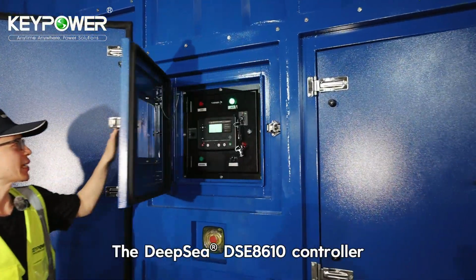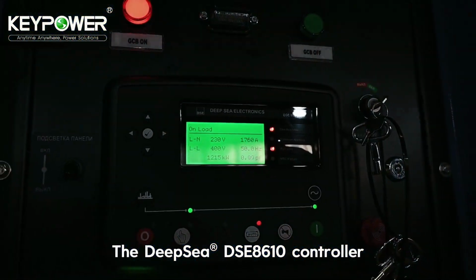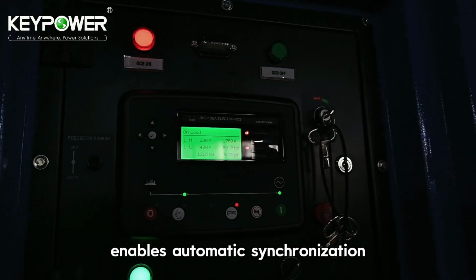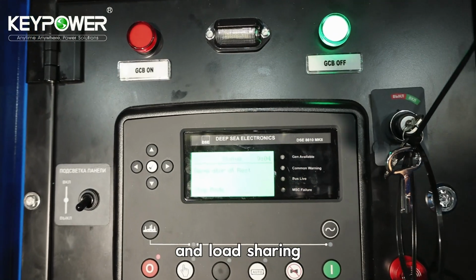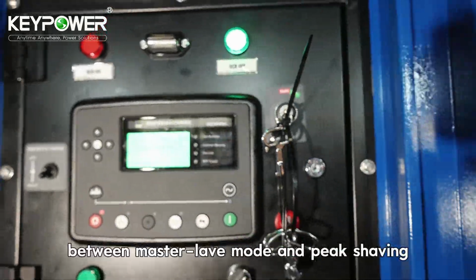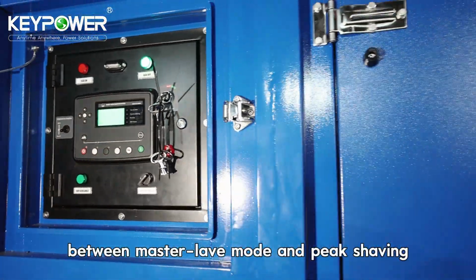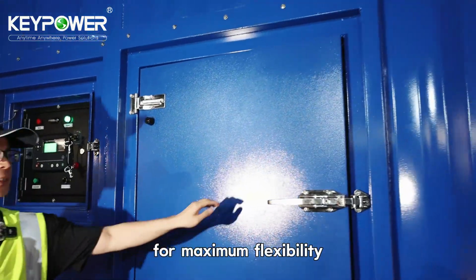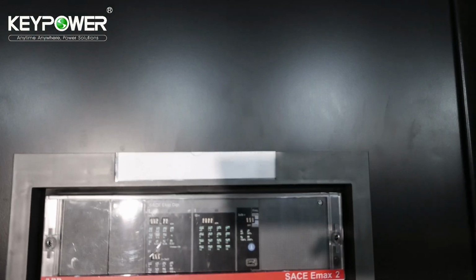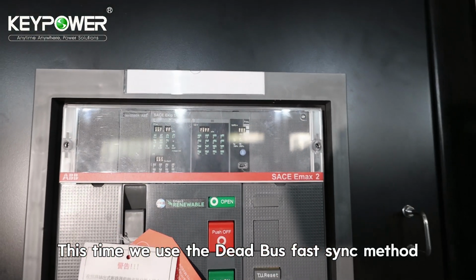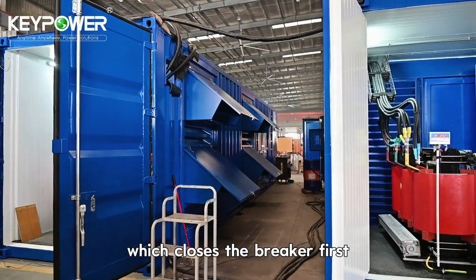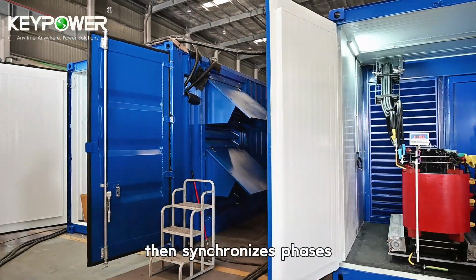The DeepSea DSE8610 controller enables automatic synchronization and load sharing, seamless transition between master-slave mode and peak shaving for maximum flexibility. This time we use the dead bus fast sync method, which closes the breaker first, then synchronizes phases.